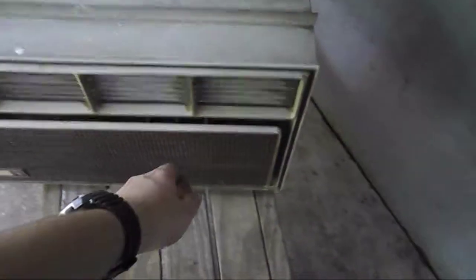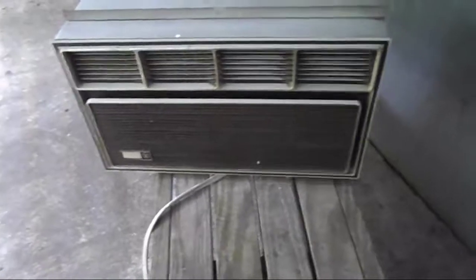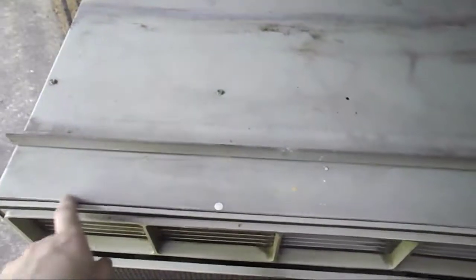So there's some stuff blowing around. I think the airflow is slightly better. Actually, these fins are down. I'd say it works pretty good. I still left that thing in there, which I think is really severely affecting the airflow on the back of the evaporator. But this is a 3-layer thick coil, so it's a little hard for the air to get through, whereas this is only 2-layer thick on the back. And as you can hear, a lot better airflow. Still a little bit of rust in there, but not bad at all.